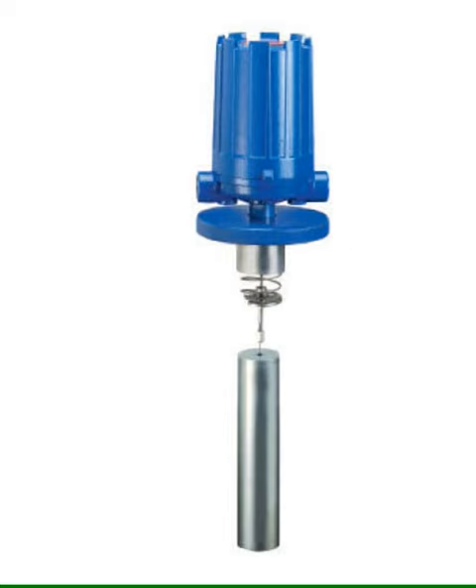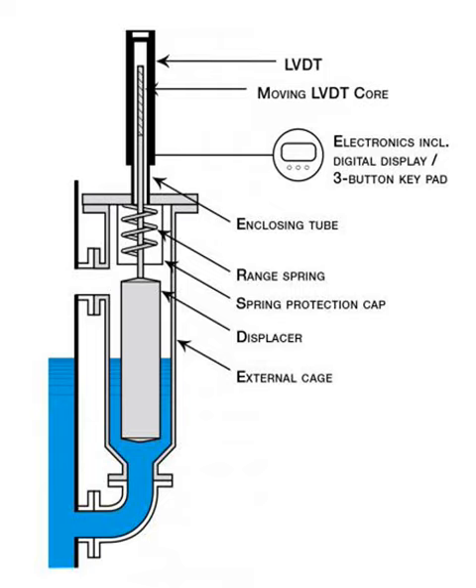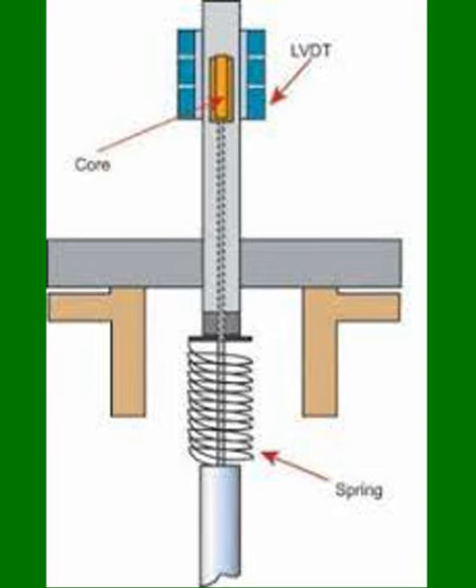A displacer-type level transmitter operates primarily on the principle of buoyancy. Picture a displacer — a buoyant object often cylindrical or ellipsoidal in shape — connected to a spring-loaded mechanism. This displacer is partially immersed in the liquid, the level of which we need to measure. The buoyant force acting on the displacer equals the weight of the liquid displaced by the immersed portion of the displacer. It's a fascinating interplay of forces, where this buoyant force is in direct proportion to the liquid level.